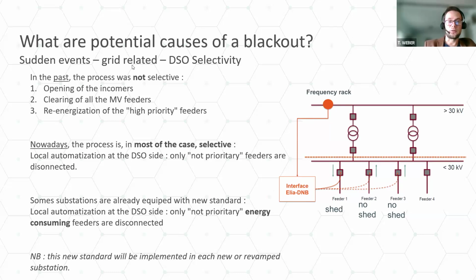And at the beginning, it was not selective. It means that all the incomers were tripped, one, two, or three, it depends on the substation of course, and the whole substation was at zero voltage. It was the first step, and then we do the clearing. So we open every circuit breaker of the feeders, except for some priority customers. I will explain that on the next slide. And then we ask Elia to feed the medium voltage busbar again, and only the priority feeders remain energized. But the big problem was that even the priority customers had an outage, and that's not the best way to work, but it was like this at the beginning.